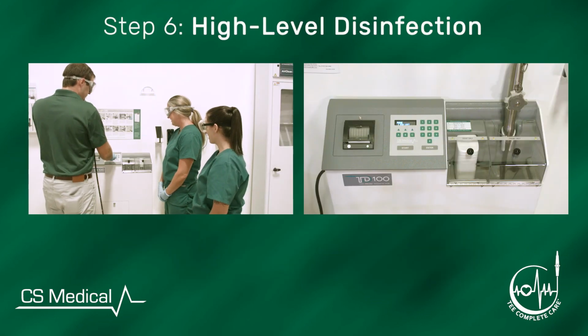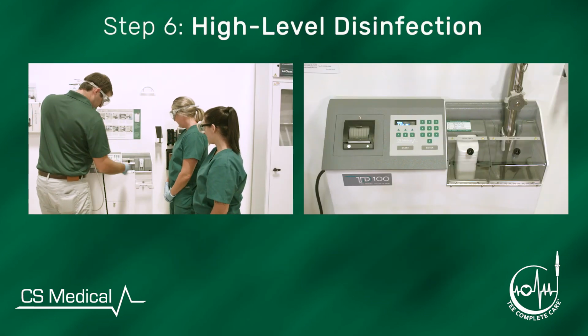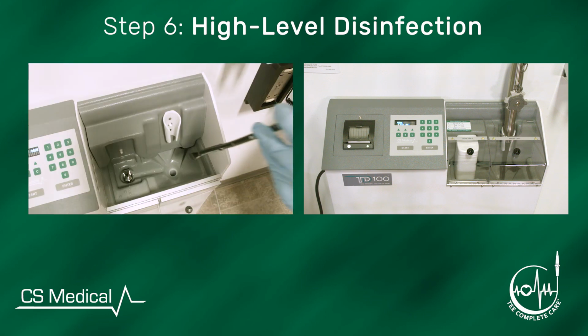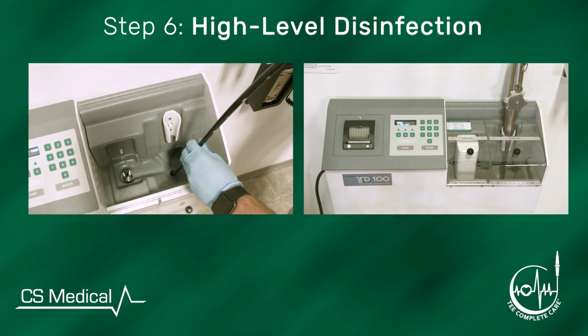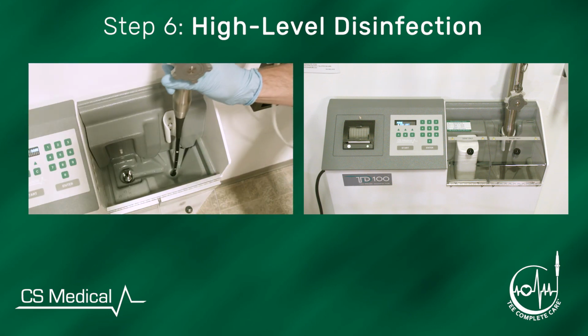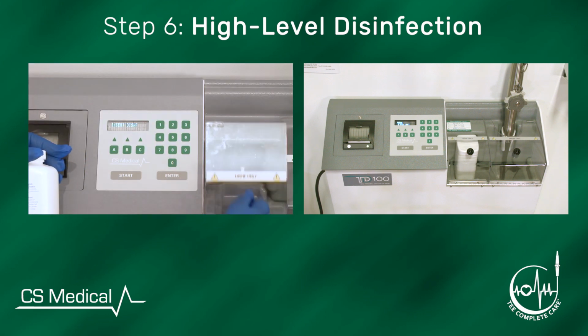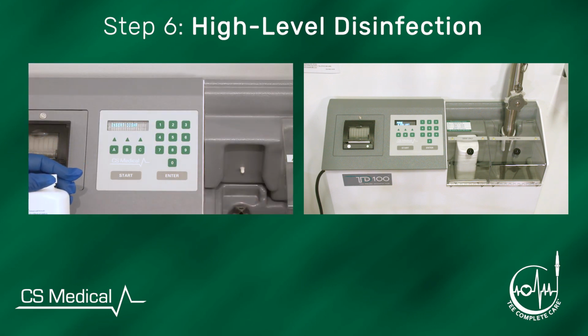Step 6. High-level disinfection of TEE probes. The TD100 automated TEE probe disinfector high-level disinfects a TEE probe in 5 minutes and then rinses any residual disinfectant free of the probe before alerting the end user a successful disinfection cycle has been performed.